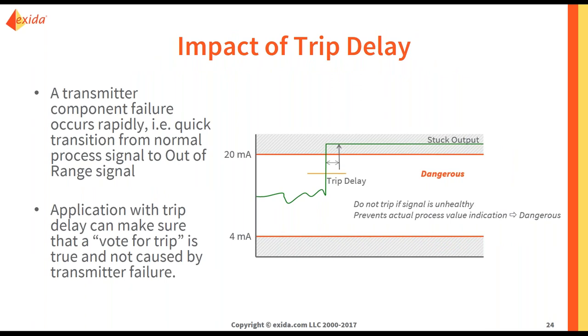There is also the impact of trip delay. Trip delays allow for a certain amount of time between a fail high and a planned trip to ensure the process value is healthy. If the value remains out of range, we know it is a transmitter issue and not a hazardous event. This would be a dangerous failure as the transmitter cannot detect a hazard and the plant is not tripping. So that is something to keep in mind.